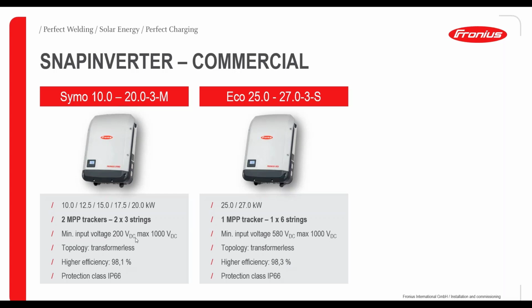The Symo has a very wide input voltage range from 200 to 1000 volts. The Eco from 580 up to 1000. So a little bit lower input voltage range. But if we consider it's about commercial rooftop or free-field installations, we talk about long strings, mostly the same direction, big PV plant. Usually we easily get there on the high voltages, no problem, with ease. Again, we have transformerless topologies and a very high efficiency, and even a little bit higher protection class, IP66 here.